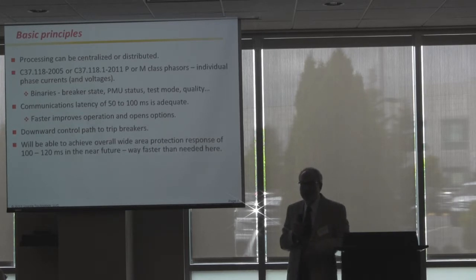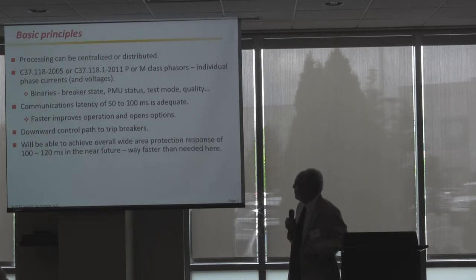For the time frames we're talking about, any of the phasor measurement methods that we have out of the standards, the 2005, the 2011 standards, all of them would work for this. We have enough time for the values to stabilize and work fine. Communication latencies that you see here, even if we're using an Ethernet wide area network, these time requirements are not at all challenging. In fact, they're already a lot faster than what we need to do this. We need a downward control path. We do have that. And we can achieve in the future, at the rate things are going, wide area protection response as little as 100 or 120 milliseconds. In fact, we probably can't set it that fast because we still have to wait for circuit breakers to do their job.